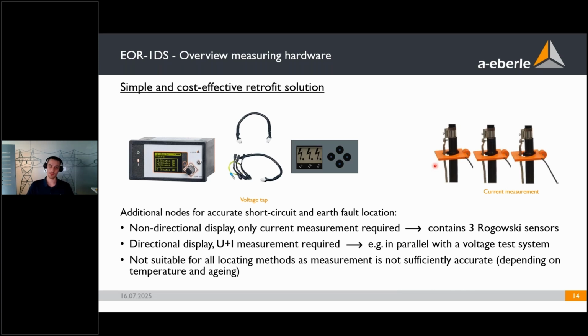For this, the simple, cost-effective retrofit solution of the EOR-1DS would be these Rogowski current measurements and capacitive voltage measurement using an LRM cable, or just one of these options. As you can see here, you can choose the option of a non-directional fault display. For this, you would only need current measurement, for example these 3 Rogowski coils or Rogowski sensors, and that way you would still be able to perform earth fault visualization using the pulse location method, or you can have short circuit indication, but that would be non-directional, as it says here. If you do want directional fault indication, you would need voltage and current measurement, for example here in parallel with a voltage testing system.